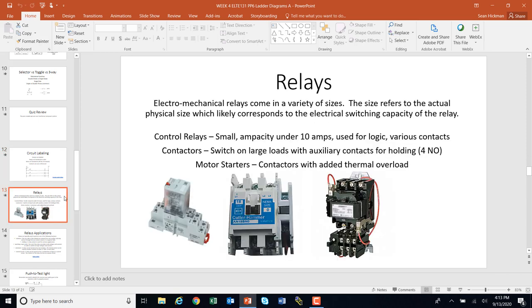Relays: we introduced relays before, but remember that in this course we're using electromechanical relays, not solid state relays. Electromechanical means there are moving parts — you'll hear them click and see them move. They come in a variety of sizes, and the size corresponds not only to physical size but to the switching capability: how many amps it can switch and the voltage of the coil. Those are the electrical characteristics of a relay.